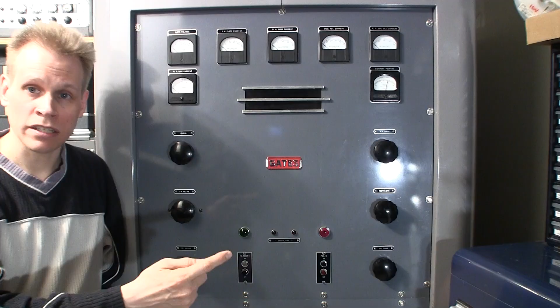To turn on the filament supply, you push this little switch right here. You'll see both of these lights glow a little dim. What's happening inside is there's a thermal delay tube that prevents the engineer from accidentally turning this thing on before all the vacuum tubes are warm. There's a mixture of two different types of vacuum tubes in here, and one of them has to wait a while to warm up. When it's warm, this light here will come on—there it is. Now it's ready to put into service.